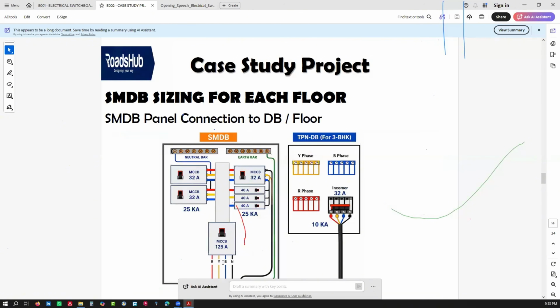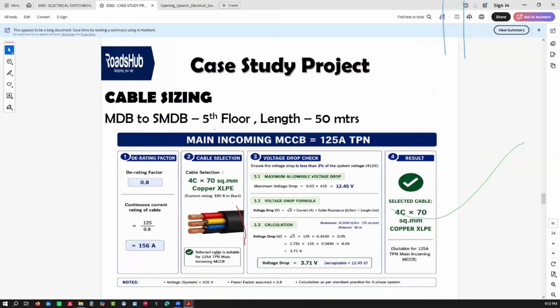So the cable that is connecting from here going to the main DBs is supposed to be rated based on 125. So when you're doing cable rating, remember we have what we call derating factors. With a division by derating factors, you'll be taking care of the cable laying conditions and temperature. You're also taking care of the cable passing through underground. We have issues there. So you put in derating factors, and the current goes higher. Demand factor, we multiply.